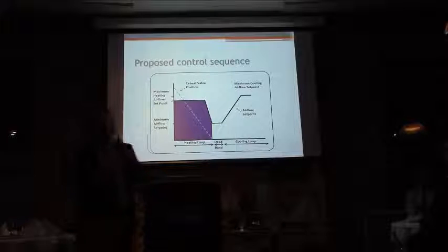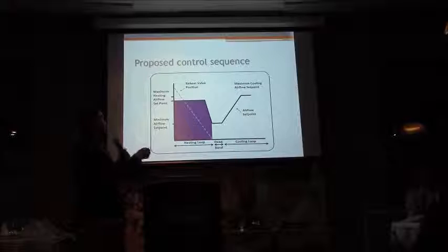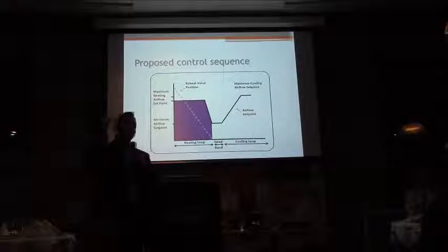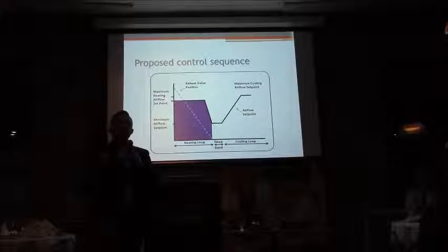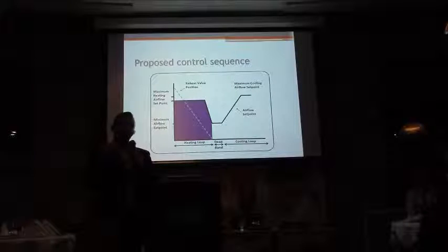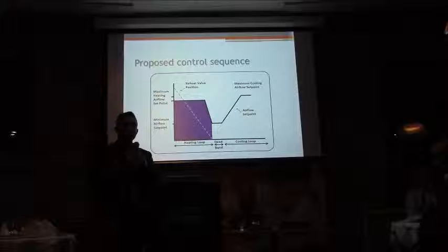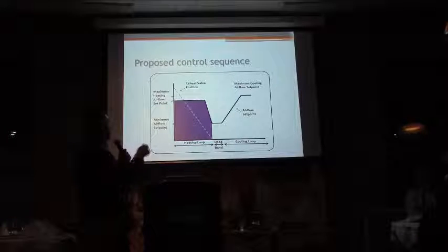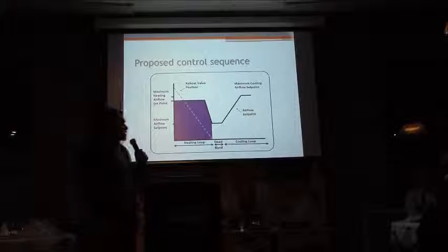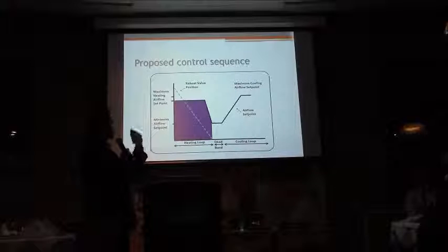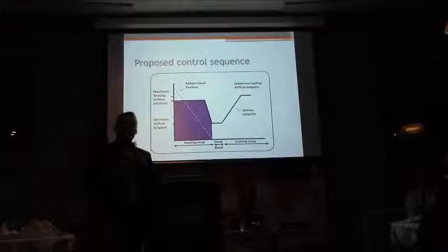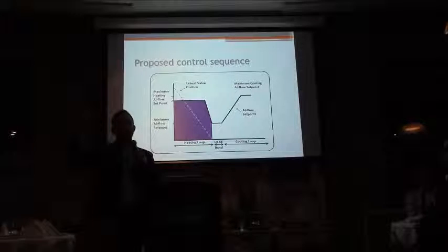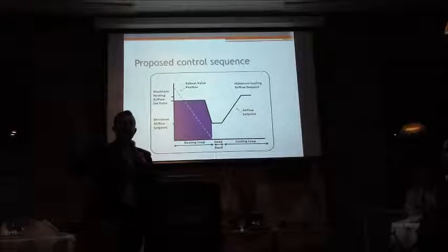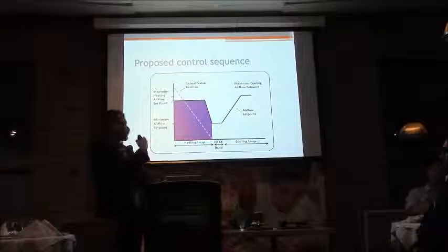The best type of control sequence we can use in Canada is something similar to here, where in heating mode, you want to be as close as possible to your maximum airflow. And in return, you reduce your delta T. So you have a bit cooler air at higher CFMs, higher velocities. So your chances of that air reaching the occupied zone are much greater than throwing hot air into a diffuser at low velocities. So if we could adopt one type of control sequence, the one I recommend is this one there. And I did one project like that in Montreal, and in heating mode we were at 80% of the maximum CFM. And some might wonder, well, if you're throwing more air, that means the fan in your air handling unit is working more. Yes, it is, that's added cost, but it's greatly offset by the energy savings you'll have by going with this control sequence.